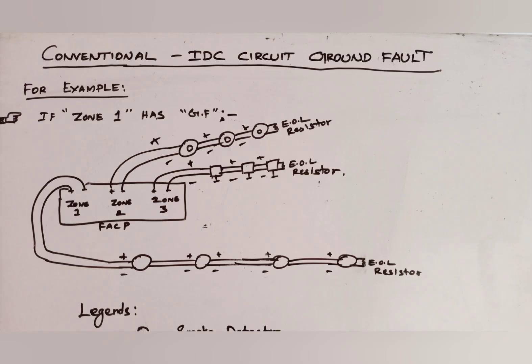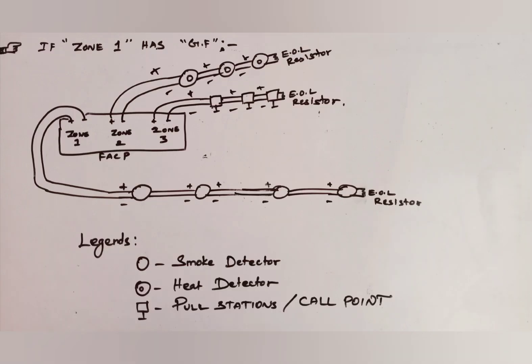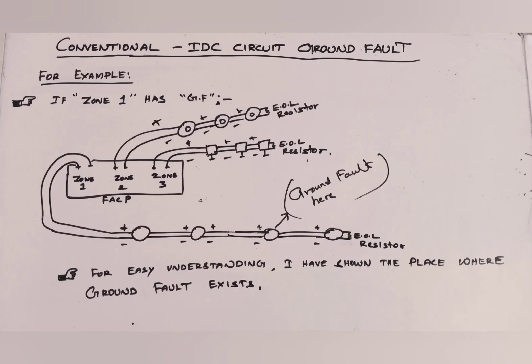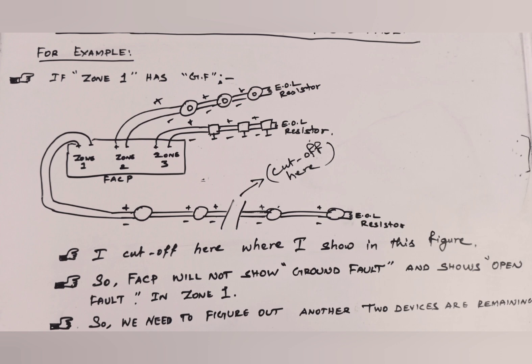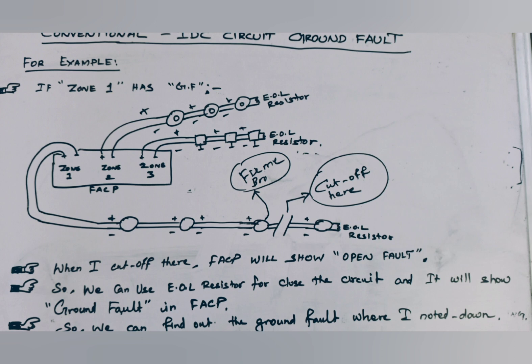So far we are troubleshooting for addressable system. Now we need to turn on the conventional system. Same as addressable system, I am showing the place where we have ground fault in zone 1 of conventional system. When I will cut off the continuity as shown in figure, zone 1 has open fault in fire alarm control panel. To avoid this problem, I am using end of the line resistor to close the loop. Then you can test the ground fault in usual way. Then you can find out the ground fault.